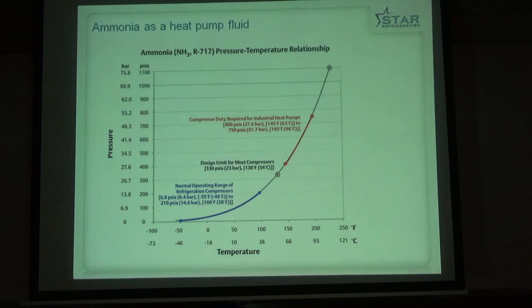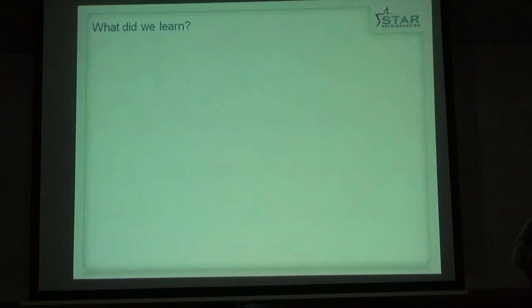With ammonia, the blue band shows you the typical operating range that we're working in for refrigeration systems between the evaporator and the condenser. And the red band shows you where we have to operate if we want to do heat pumps. So in order to get the higher temperatures, we're having to operate at higher pressures. And that brings a whole bunch of challenges in designing the system. So what did we learn from doing these systems?